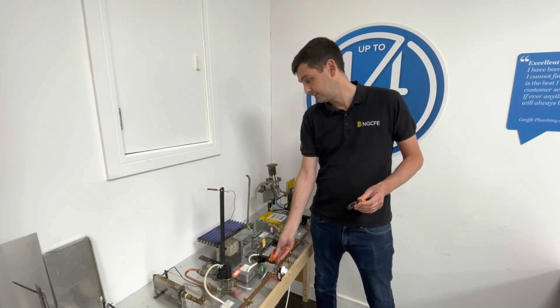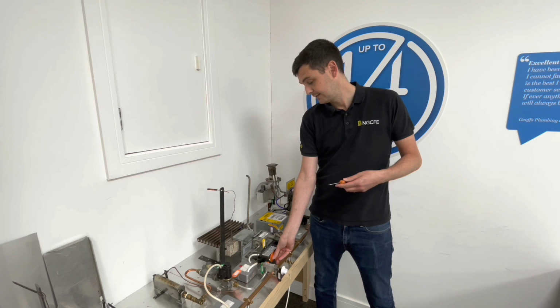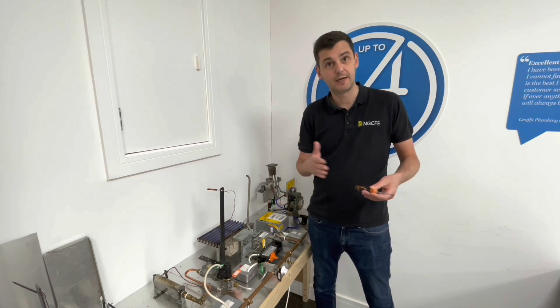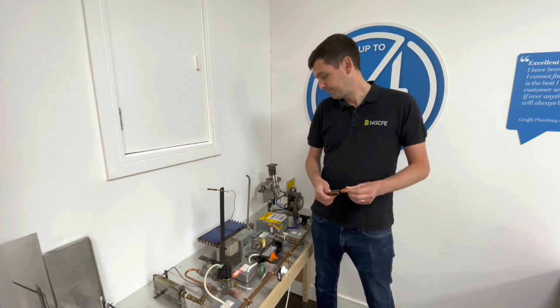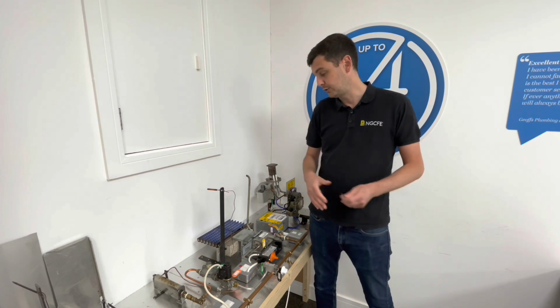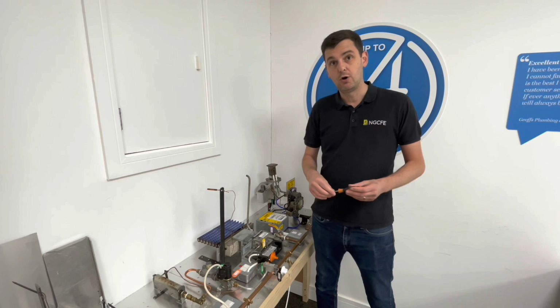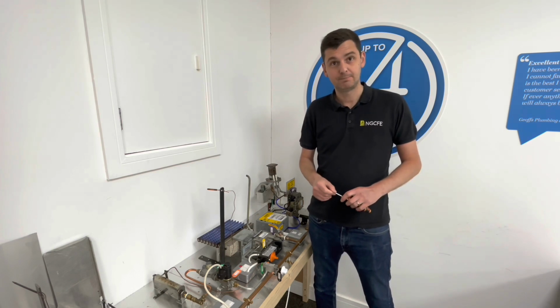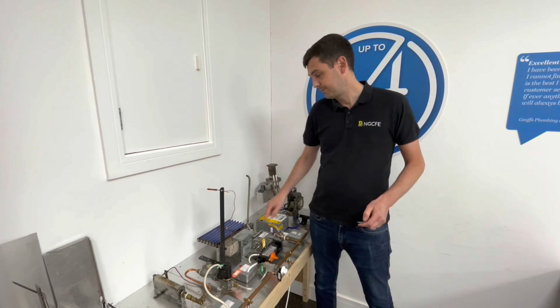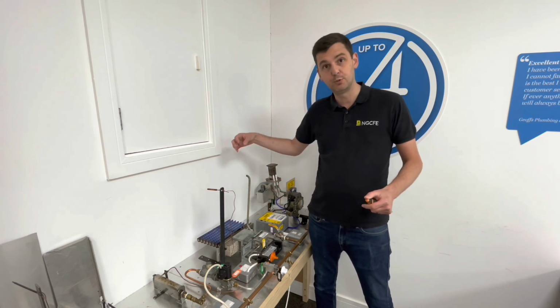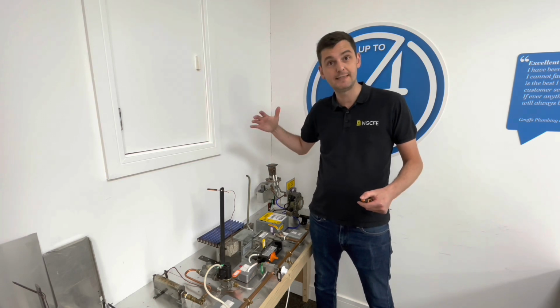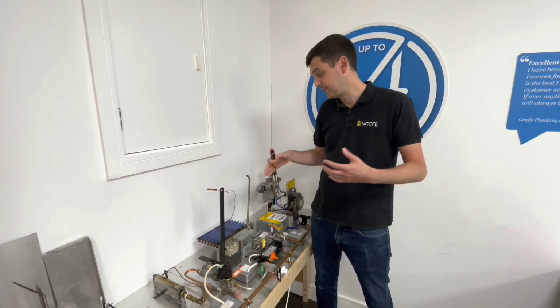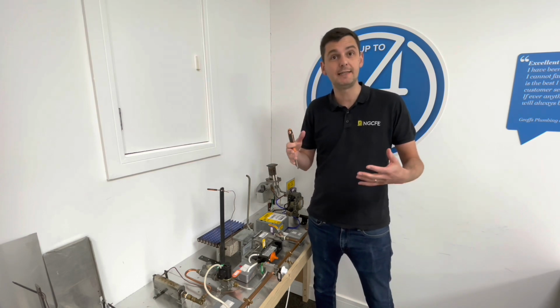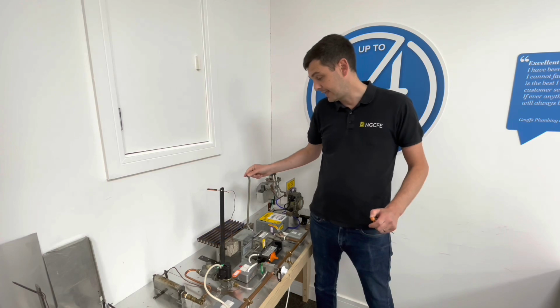So all you'll see is, once it gets to temperature, it'll turn off, and then once it gets cool again, it'll come back on, and it'll just do that and maintain the temperature that we want in the property throughout the day. The other control that we do have on this, one thing that we do need to note, is that we've got what we call an ODS, an oxygen depletion sensor. On this unit, it takes its air for combustion for the pilot light from above the unit, above the heat exchanger. So the idea is if the air above the heat exchanger was vitiated or depleted in oxygen for whatever reason, it would then turn off.